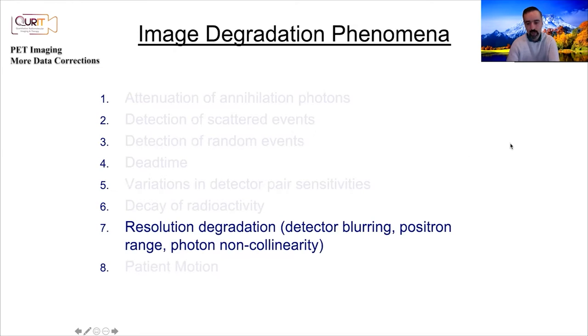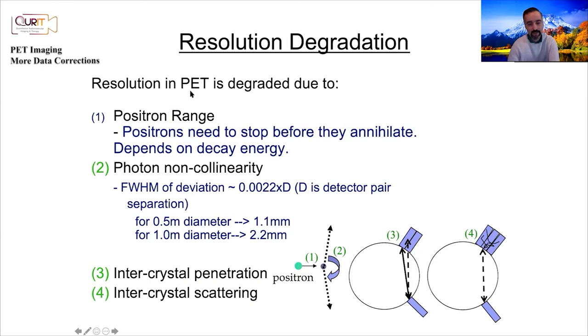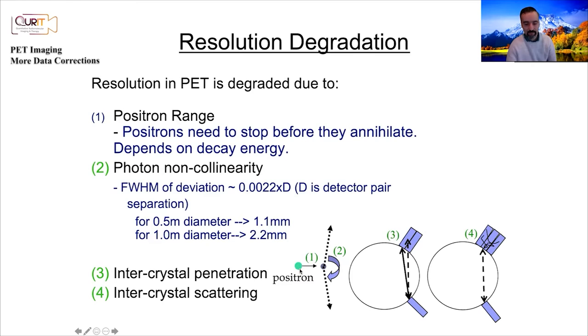Resolution can be degraded in PET due to several events, some unique to PET. One is positron range — positrons need to slow down before they combine with an electron to annihilate. For Fluorine-18 the range is around 0.22 mm; for Rubidium it can go up to 2 mm. The event starts at one location but the positron travels a sub-millimeter distance before annihilating, which limits resolution.